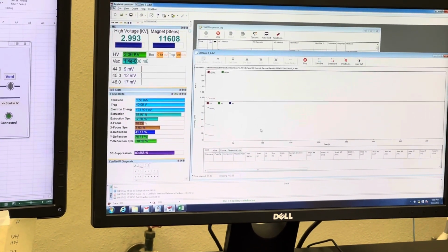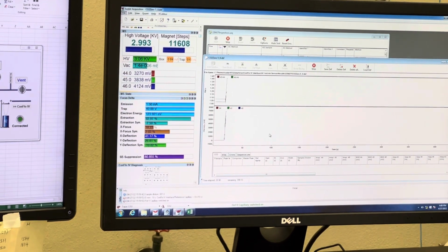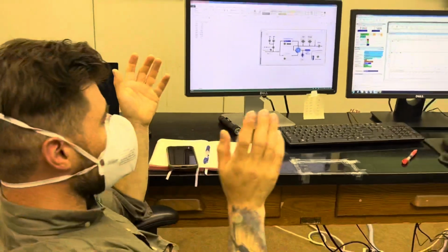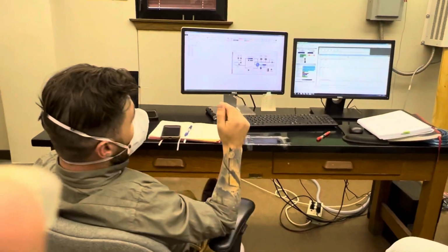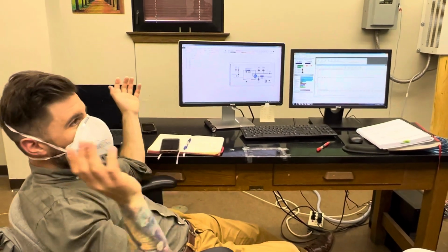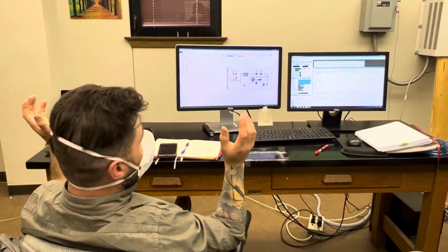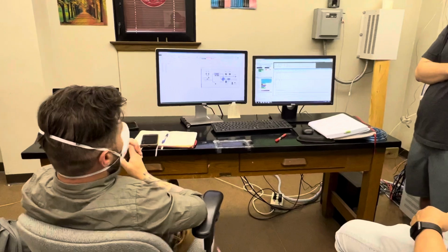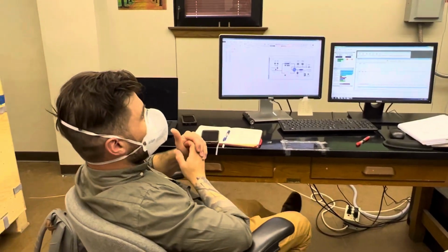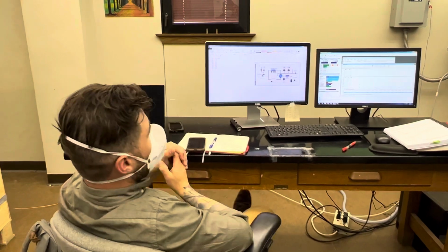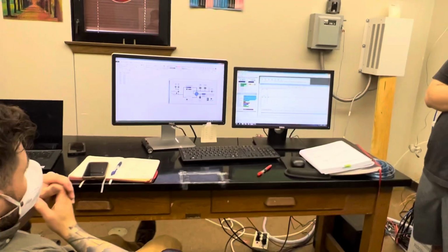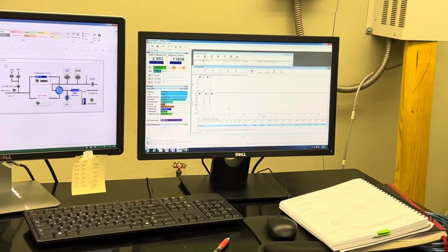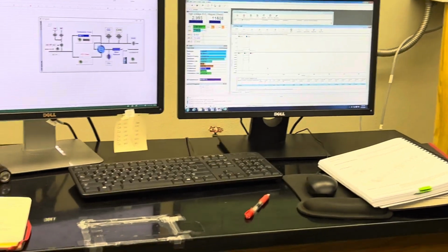So that's how you describe this guy, that it's built for precision, not accuracy? Yeah, this is all precision. I don't know how wrong I am with this either. If you want something that's accurate, you have mass spectrometers the size of this room. They're large mass spectrometers that are used for accuracy. Those are the accurate ones. I don't know how you come up with accuracy. I have to sit down and think about that for a really long time. But these and the 253 are built for precision.